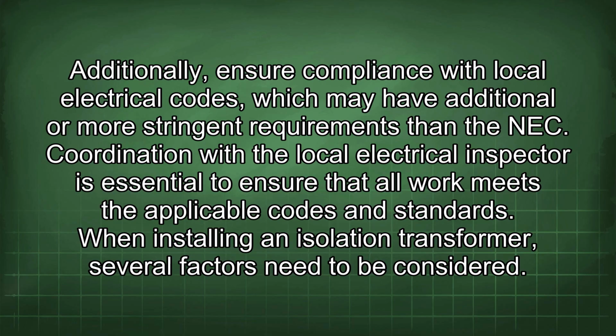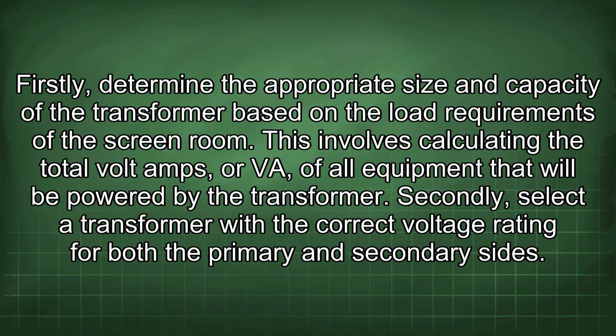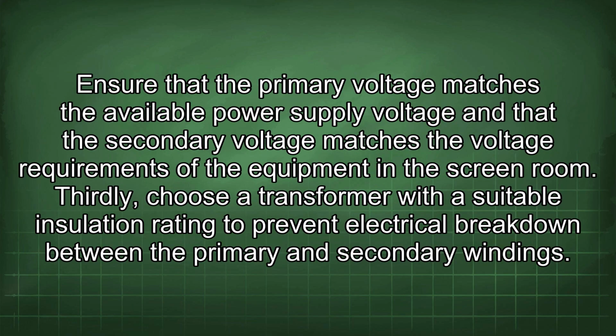When installing an isolation transformer, several factors need to be considered. Firstly, determine the appropriate size and capacity of the transformer based on the load requirements of the screen room. This involves calculating the total volt-amps (VA) of all equipment that will be powered by the transformer. Secondly, select a transformer with the correct voltage rating for both the primary and secondary sides. Ensure that the primary voltage matches the available power supply voltage and that the secondary voltage matches the voltage requirements of the equipment in the screen room.